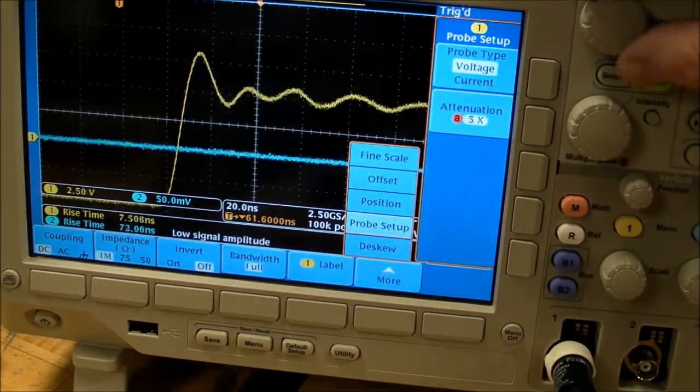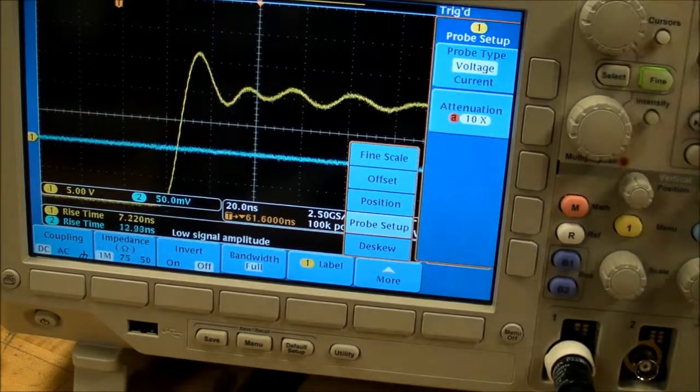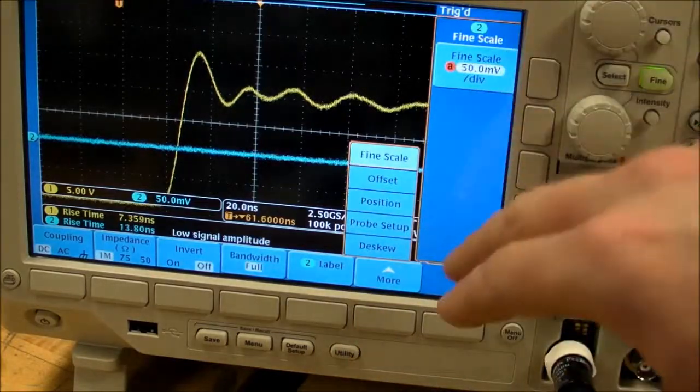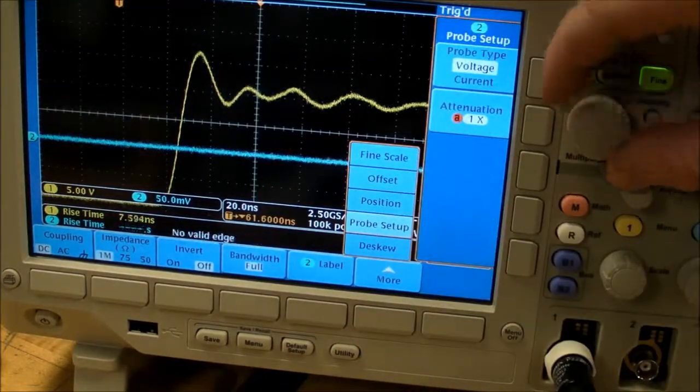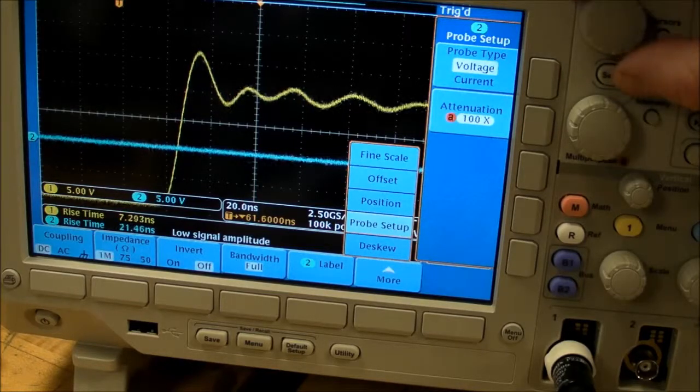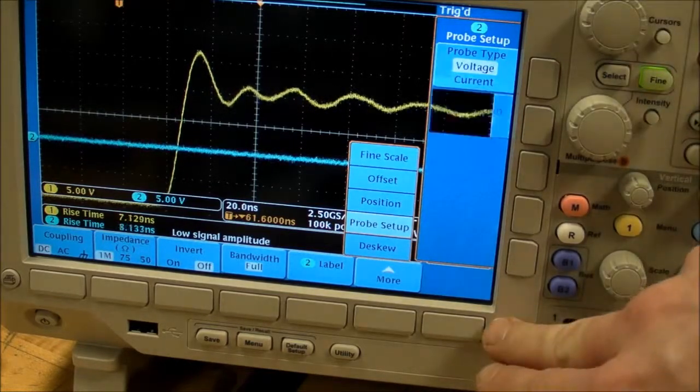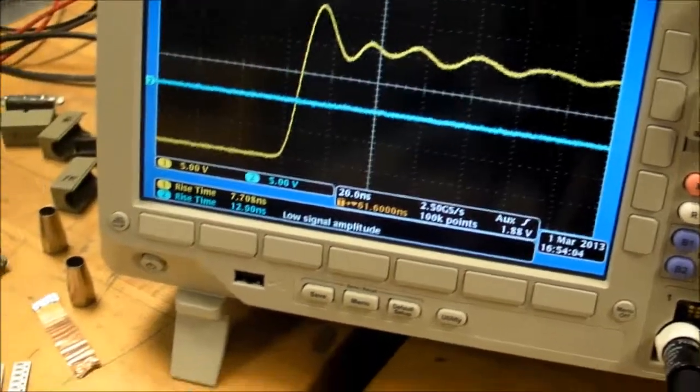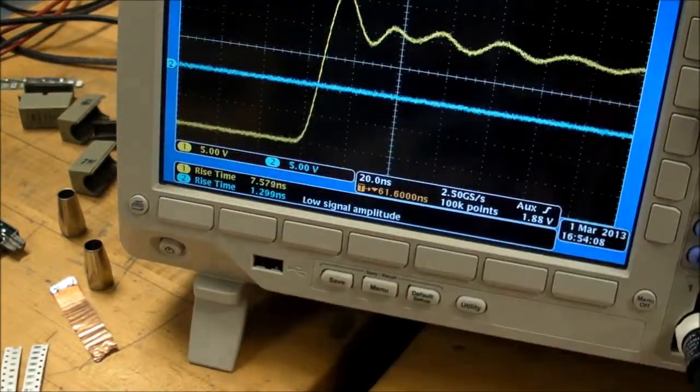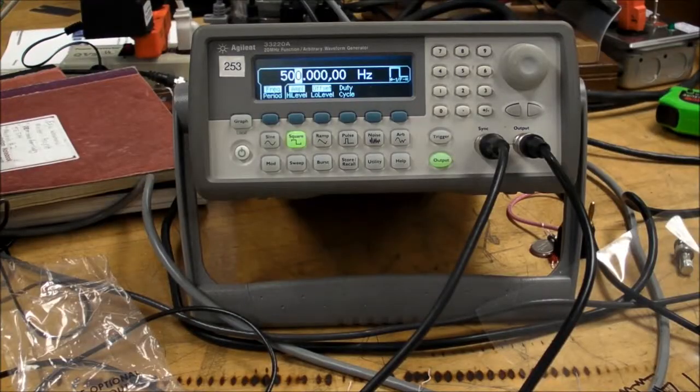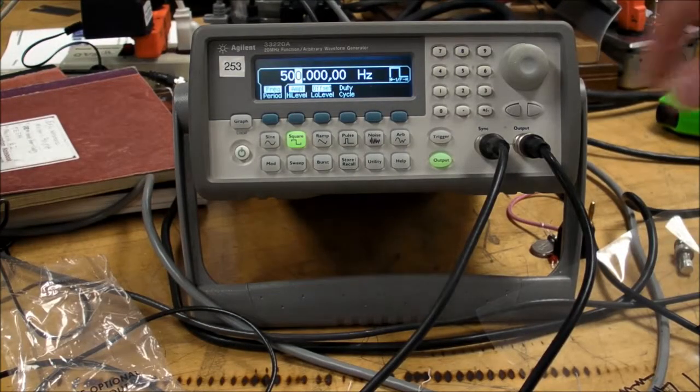Let me change channel 1 here, attenuation to 10x, because that's the probe I got in there. And then channel 2, where I'm putting my new probe, put that on 100x. And then both of these, channels 1 and 2, should be the same voltage per division. All right, that's enough talking about the probe. Let's see it working.